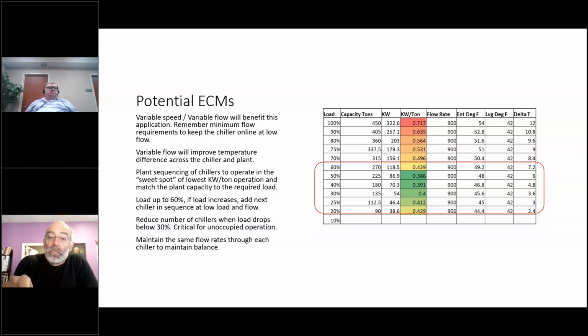But that aside, the question I have is on the delta T column, because our assumptions are often wrong when we walk into these mechanical rooms. But the delta T, where you're saying this chiller is doing the best, is really low. In fact, you're saying even a 2 or 3 degree delta T is really good. Whereas the conventional wisdom is, no, you want a 10 degree delta T or a 12 degree delta T. Yeah, that's what we want. Otherwise, we're going to have real problems with the chiller. Can you discuss that?